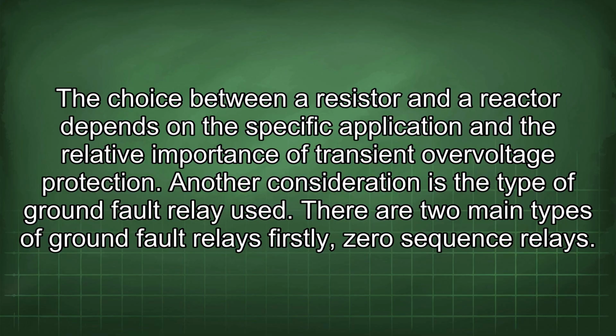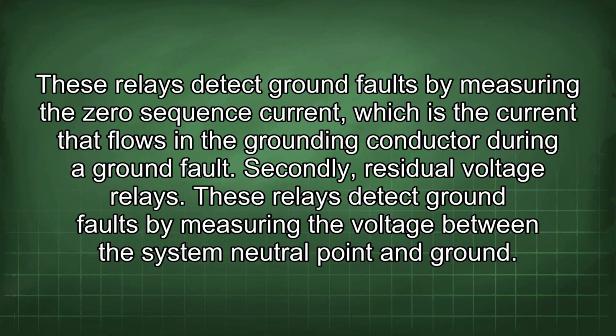Another consideration is the type of ground fault relay used. There are two main types of ground fault relays. Firstly, zero-sequence relays. These relays detect ground faults by measuring the zero-sequence current, which is the current that flows in the grounding conductor during a ground fault. Secondly, residual voltage relays. These relays detect ground faults by measuring the voltage between the system neutral point and ground.